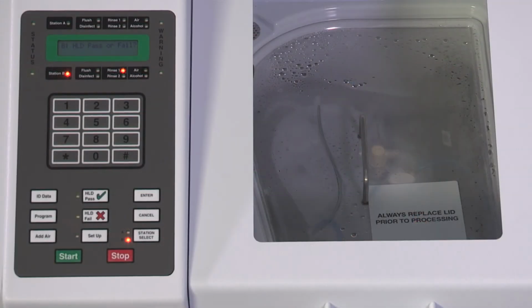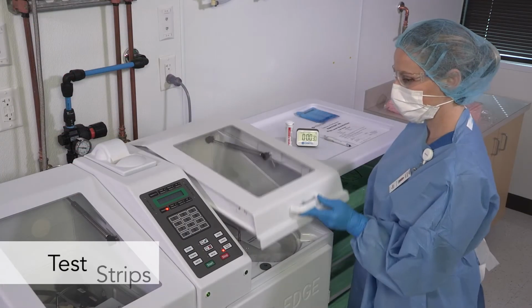Phase indicators identify which cycle phase the system is performing. The LED illuminates to indicate the present cycle phase. The air light will flash at the end of each cycle phase to indicate air is being pushed through the channels to facilitate purging. When the disinfection process is complete, the display prompts the operator to test Rapicide PA Disinfectant's MRC with a test strip.